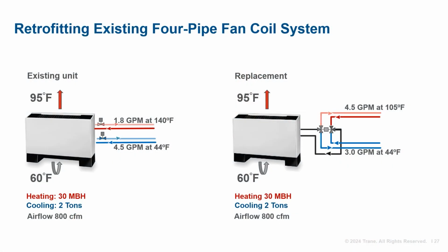It is important that the replacement unit does not take up any additional space due to the value of finished space in a commercial building. There is no extra room for 8 rows of coil, so we must stick with 4 rows. Because both the hot water and chilled water supply come from the same central equipment, the same coil can be used for both heating and cooling. But how is this achieved? How do we switch the fluid temperature provided to the fan coil from heating to cooling and vice versa?